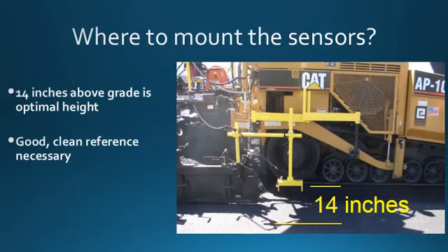The sensors compensate for this, but it's still best practice to mount the sensor a bit closer to grade than the maximum range would allow. 14 inches is the optimal height, and of course the sensor needs to be measuring over a good clean reference, because this reference is what the controls will match.